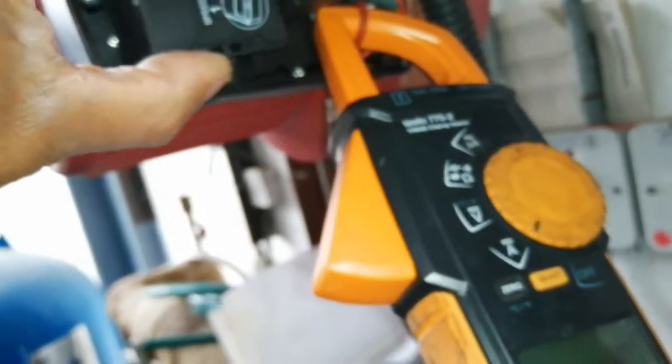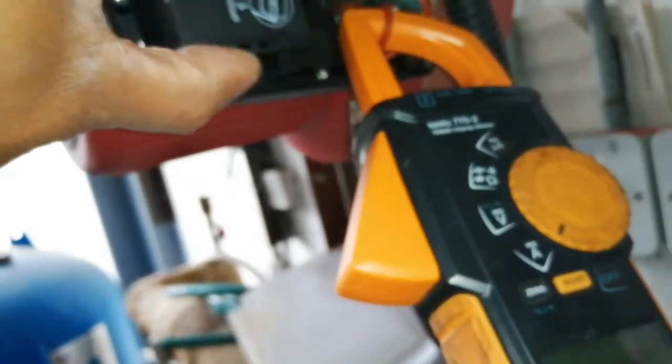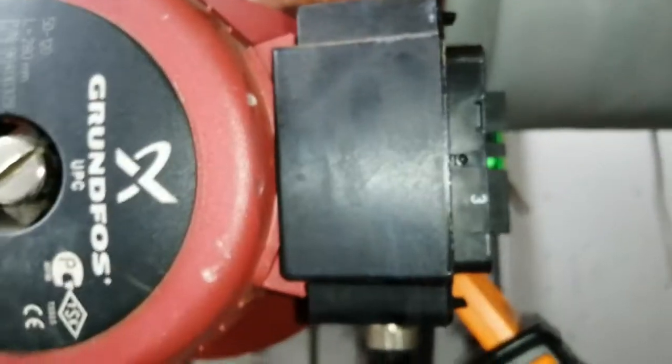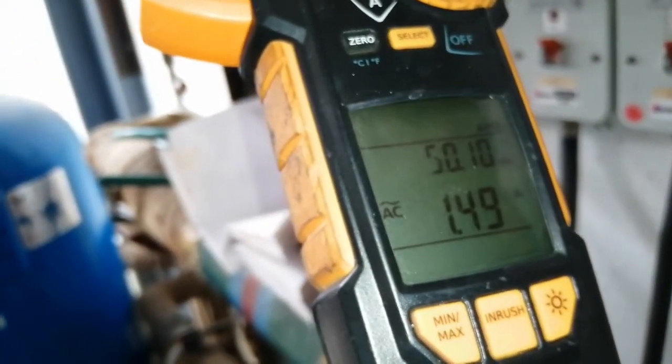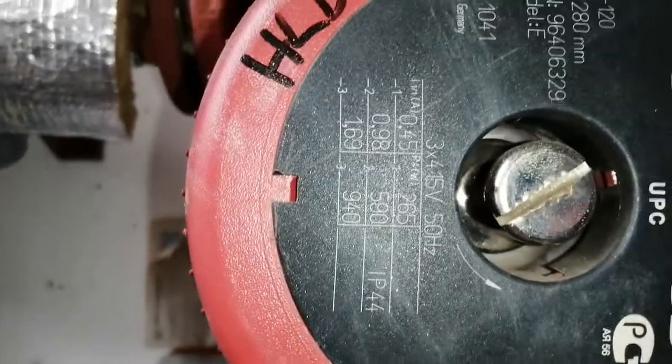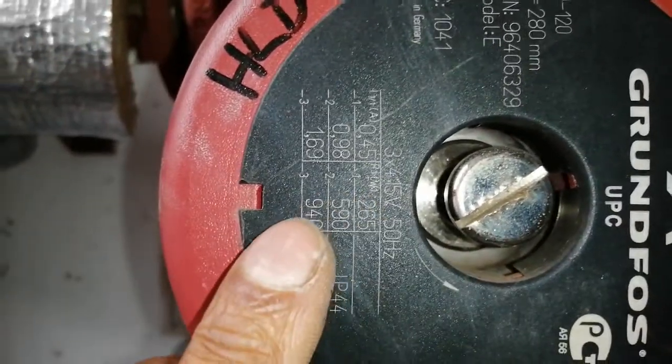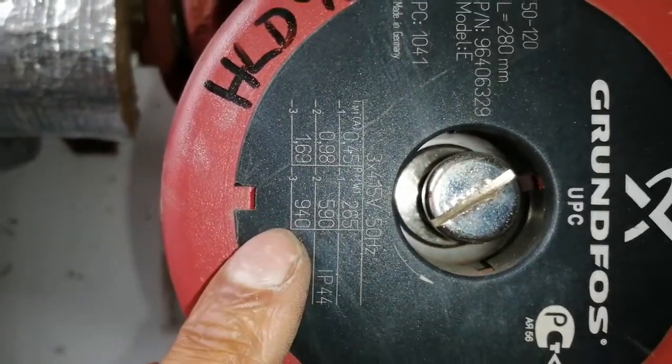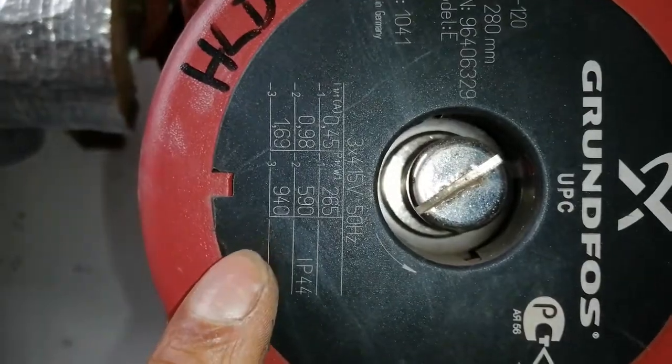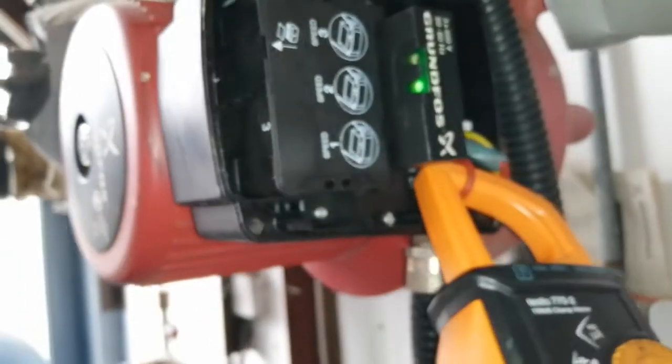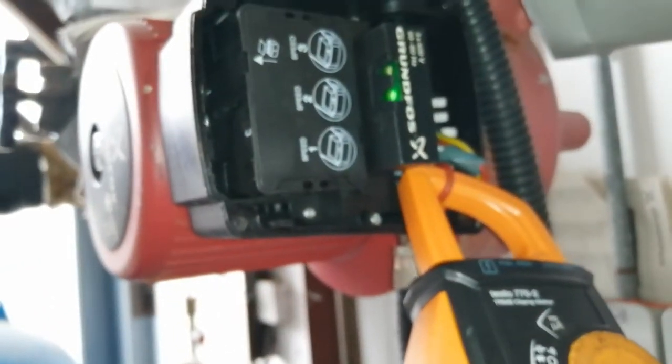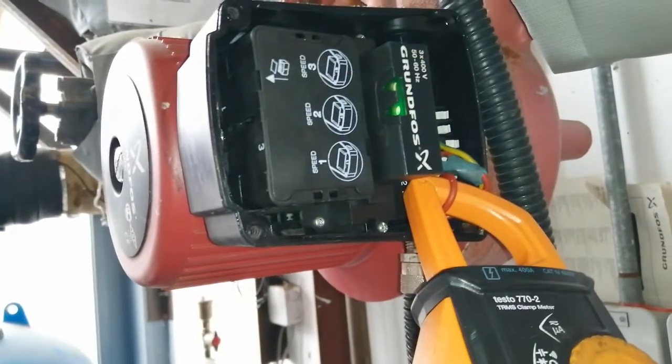It's coming back to speed 3, how I found it. 1.49 on one phase, 1.69 maximum. Okay, looks like it's operating quite well. But that's just changing over the speeds on this Grundfos pump.